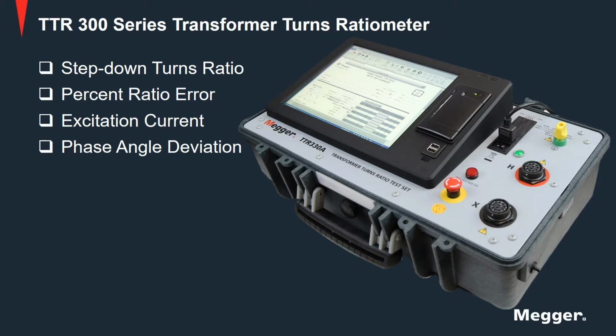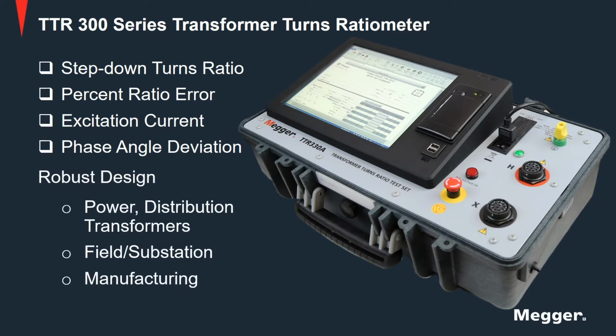In addition to turns ratio, the unit measures percentage ratio error, excitation current, and phase angle deviation between the high and low voltage windings. The TTR300 series test sets are designed to measure the turns ratio of power transformers and distribution transformers in a substation or manufacturing environment. A rugged and robust design makes these instruments well suited for use in a variety of harsh environments. Our leads are specifically designed to provide the necessary flexibility needed in cold weather.